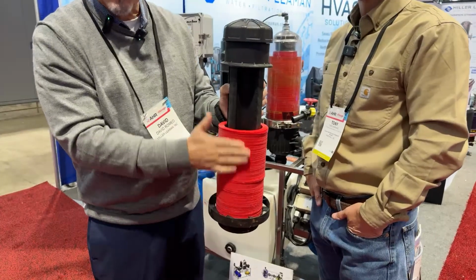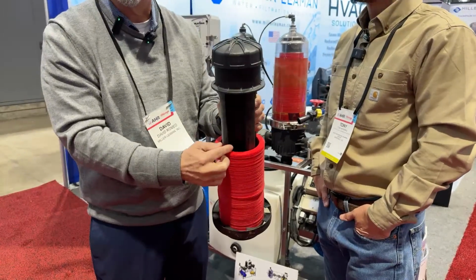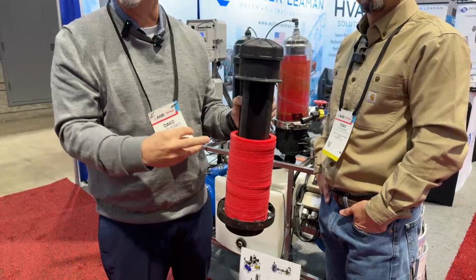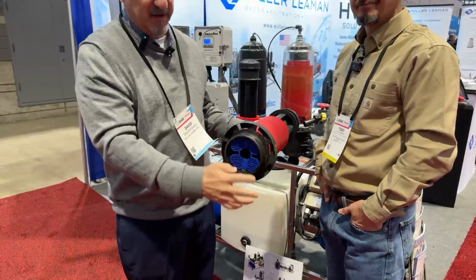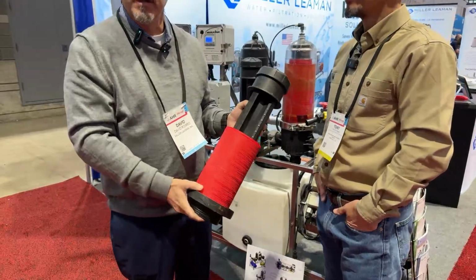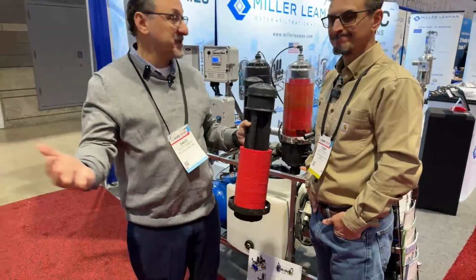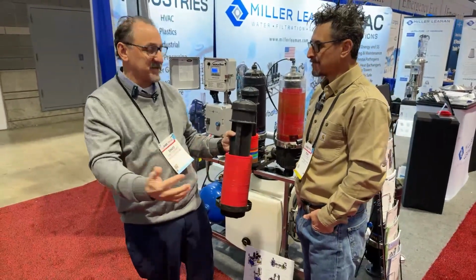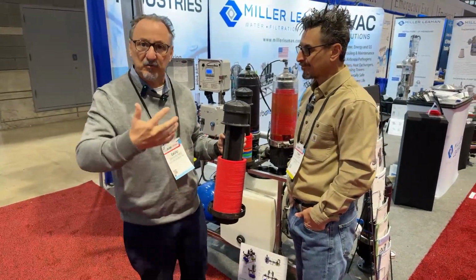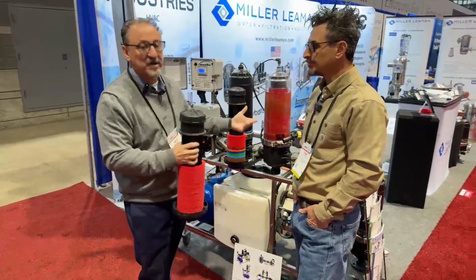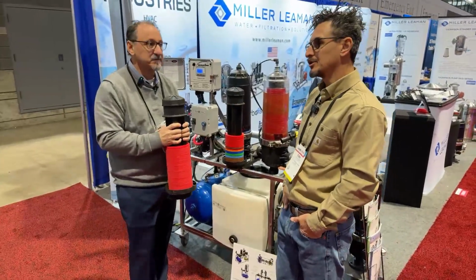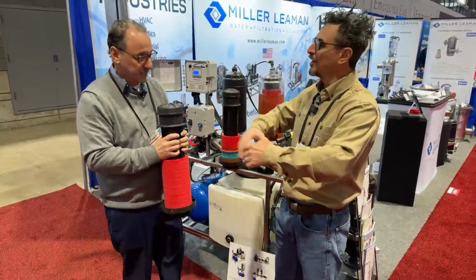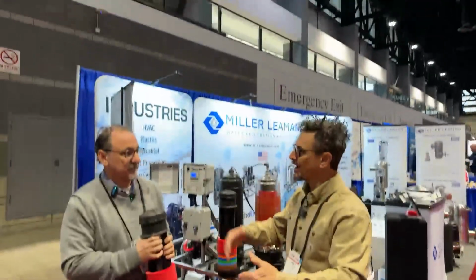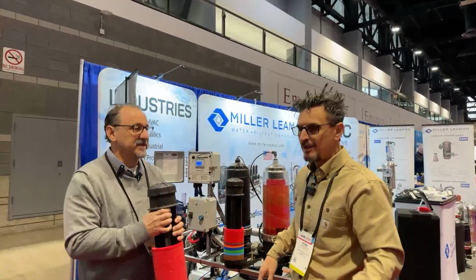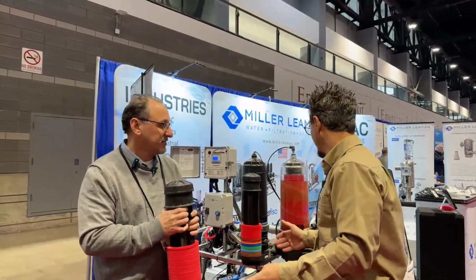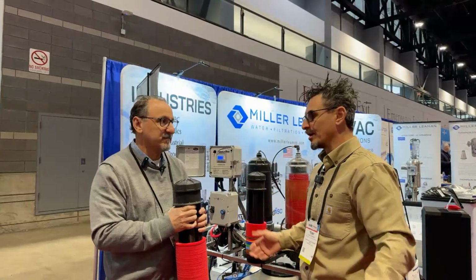You have the surface area, and then you're polishing the water with the depth, capturing the organic and non-organic particulate, coming out the bottom, going downstream from there to the process. Maybe through a sweeper system on a cooling tower at the bottom of the tower, keeping it agitated, keeping the particles moving in that tower so our filter can pick them up and remove those particles. Right, so the sweeper system keeps the basin water flowing. It pushes everything towards the drain so you can pull it back here, remove it. Exactly. We've done a ton of these with our company and our cooling towers, and it keeps the water really clean.